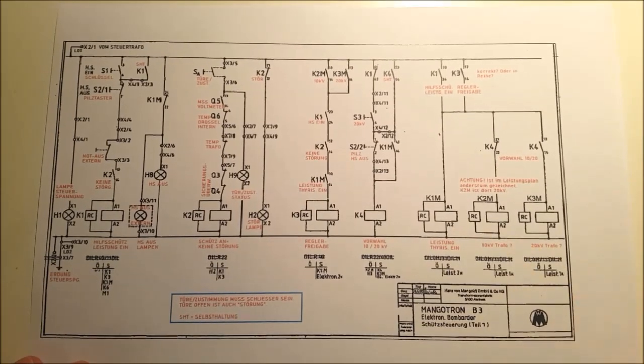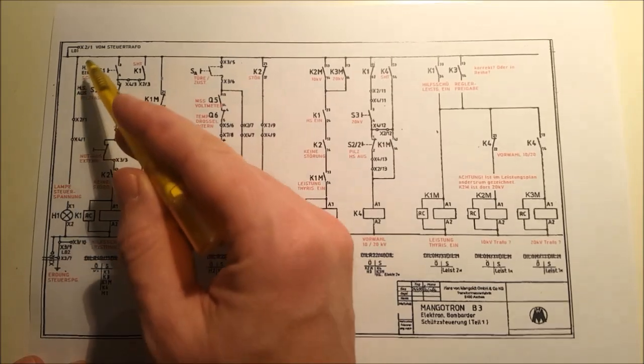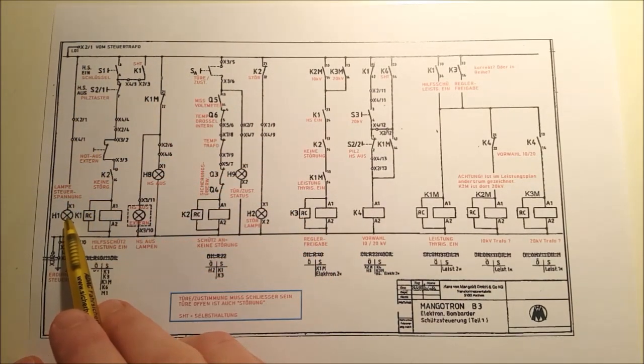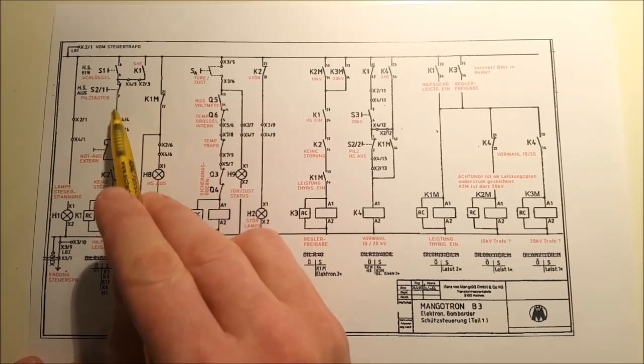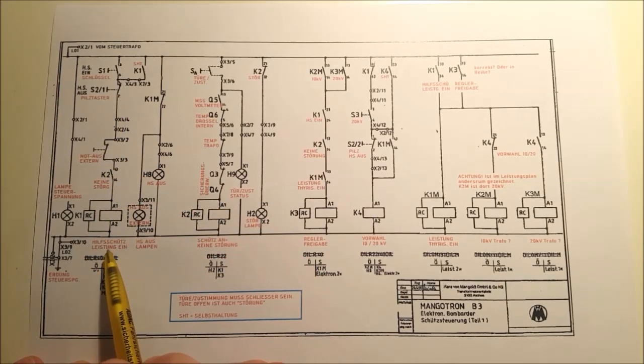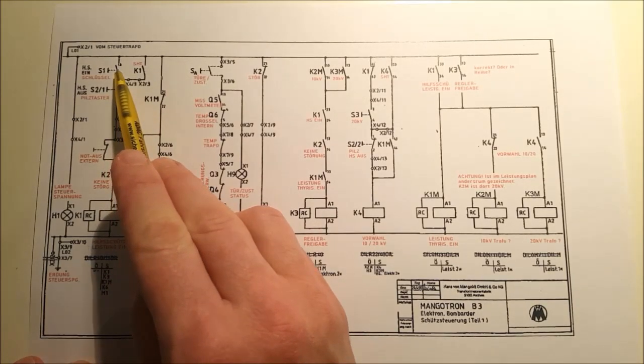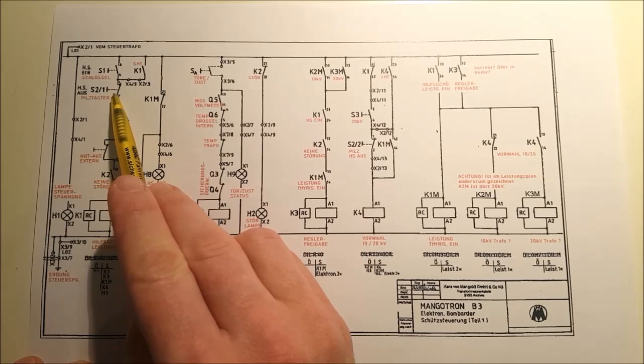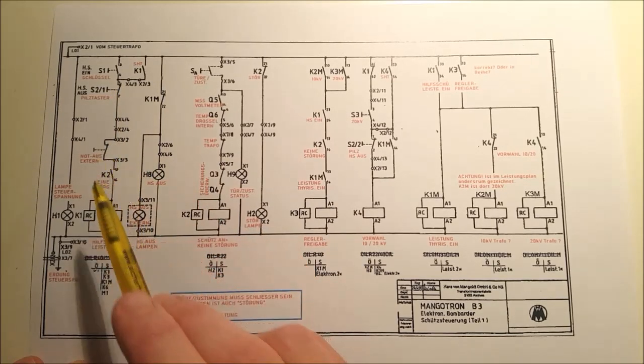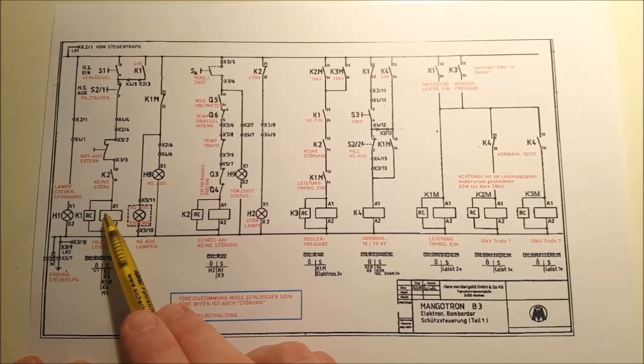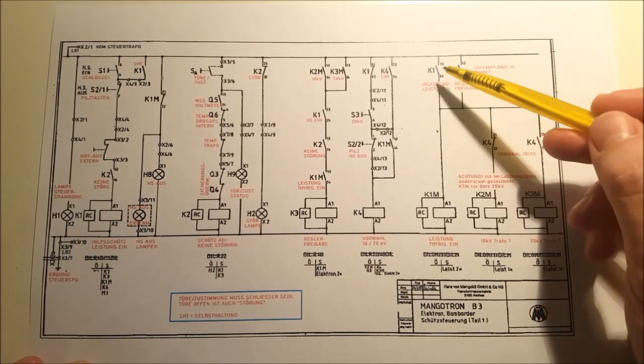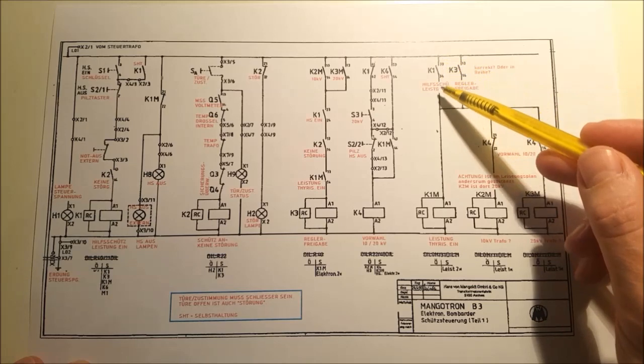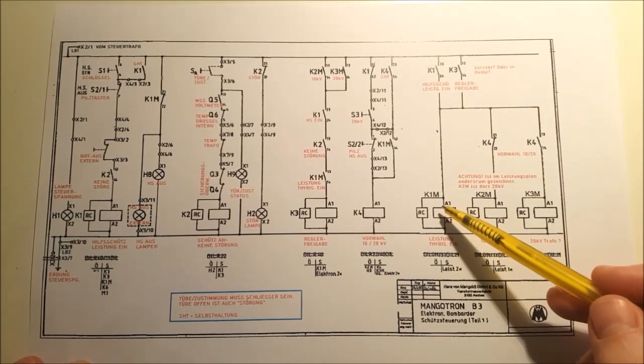And this is the contactor control circuit. You see that I added my own comments when I deciphered that page, and it's not as difficult as it looks. So this first lamp just shows the presence of the control voltage, and then this first current path here is an auxiliary contactor for main power on. So if you turn the key switch, the stop switch is not pushed, the emergency off is not pushed, and there is no error, then this auxiliary contactor pulls in, and that immediately turns power through to this main contactor K1M.